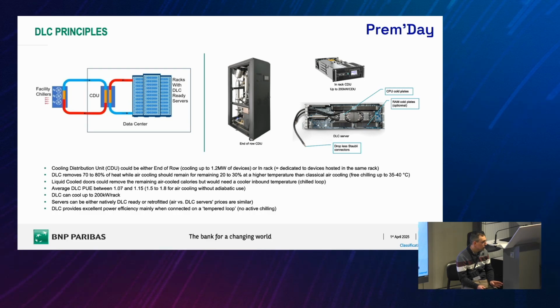And DLC is able to cool up to 200 kilowatts per rack. It's also the maximum that we saw in one of our DLC facilities. The capability of the supplier to cool can reach 200 kilowatts per rack. The servers are also provided by standard server suppliers, so I won't name them, but you know them perfectly. They have a DLC section. Most of their machines are available in DLC, natively DLC. And we also consider that since we are using DLC, we are beginning to have a vision on the decrease of outages on the servers. It means that DLC potentially decreases the number of hardware failures because the hardware is more properly cooled and potentially more robust to heat issues.